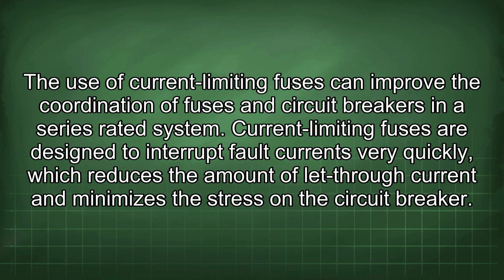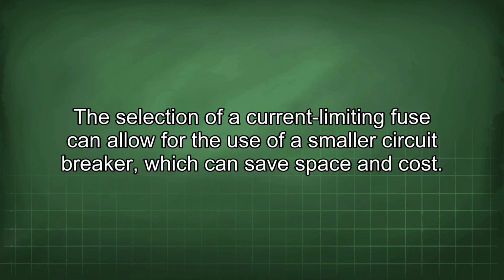The use of current-limiting fuses can improve the coordination of fuses and circuit breakers in a series-rated system. Current-limiting fuses are designed to interrupt fault currents very quickly, which reduces the amount of let-through current and minimizes the stress on the circuit breaker. The selection of a current-limiting fuse can allow for the use of a smaller circuit breaker, which can save space and cost.